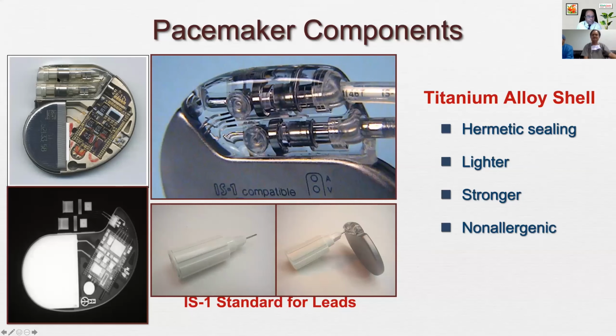And as we can see in this picture, in the left panel, we have the pacemaker battery, we have the electronics, and we have this header, which has two receptacles in this case, because it's a dual chamber pacemaker, and the lead can be inserted in each of these. This IS-1 standard lead, as we can see printed here, has to be screwed. The shell of the device is usually a titanium shell, which provides a hermetic sealing so that no body fluid can enter the device. It's very light, strong, and non-allergenic. So a titanium alloy has become the standard for these devices.